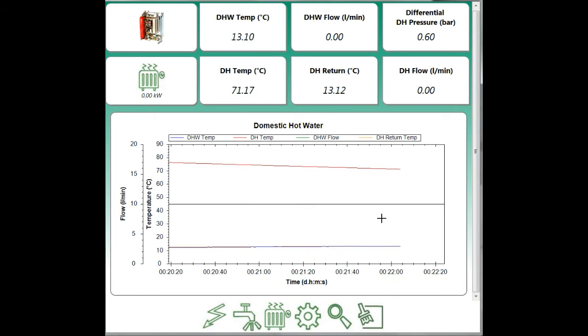Initially, not much happens because the unit is only allowing very small amounts of water into the plate heat exchanger to warm us up. Now we can see the start of that to happen now with a slight drop in the district heating return temperature. This is probably due to a small amount of cold water in the bottom of the heat exchanger being expelled.